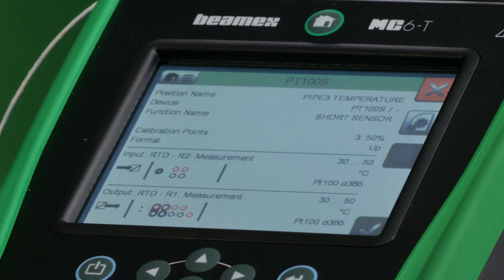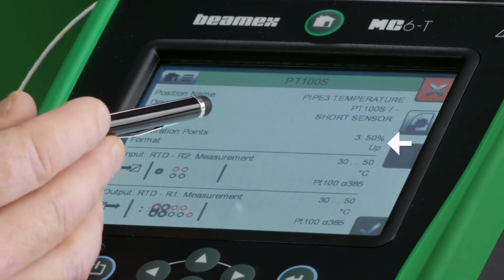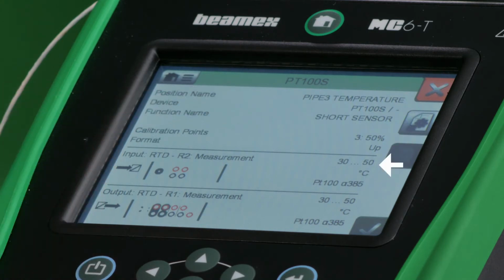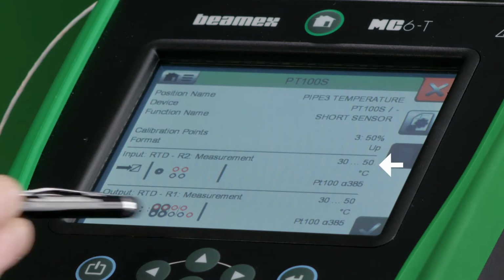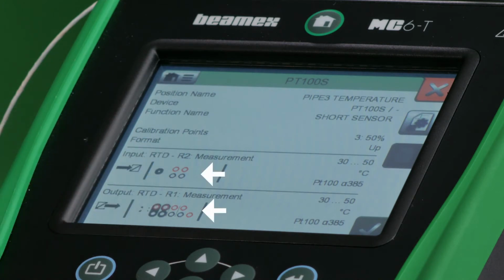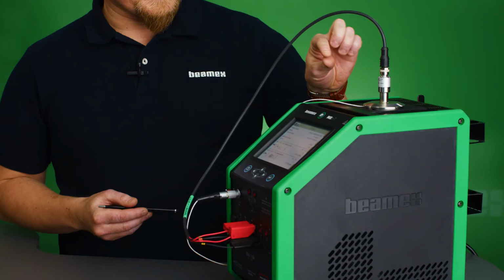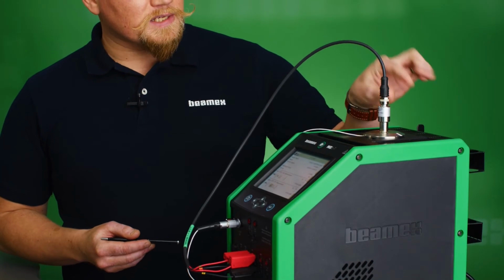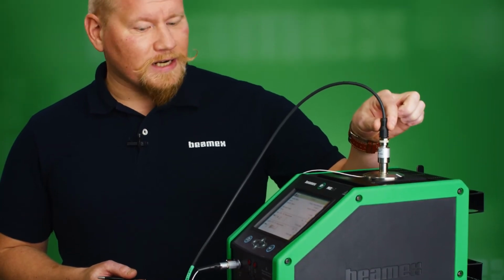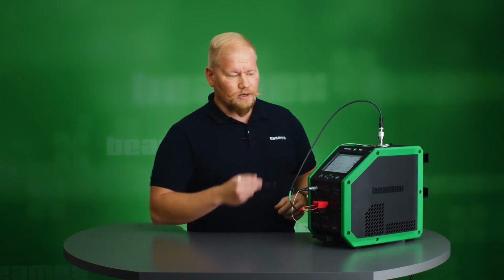The information I see here is, for example, the position name and the device. I see my calibration points. In this case, I'm going to be doing 3 points up. My range is going to be 30 to 50 degrees Celsius. And I also see how to do my connections. I've already placed my special insert here. I have my reference in place. I have my short sensor that I need to calibrate, and everything is connected. I'll hit start.